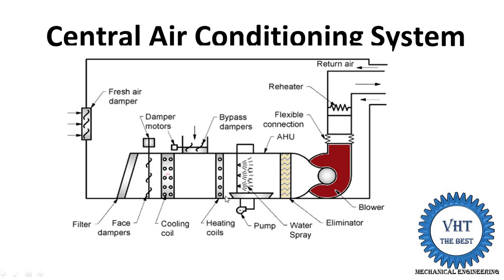During winter seasons, when heating is required, we operate the heating coils — an electric heater or similar heater is used. Fresh air comes in and passes through the heaters. When heating is required, the cooling coil is stopped — the refrigeration system is closed. When cooling is required, the heater is off. In winter, when heating and humidification are required, we turn on the heaters and spray water for humidification, increasing the humidity before the air is supplied to the room.